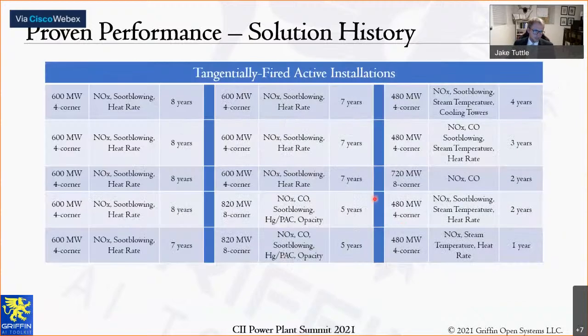Very quickly, just a brief history: we've been doing this over the past 8 years. All of these are closed loop control, meaning the operator simply turns the system on and it's optimizing from there on out, determining the optimal operational parameters. Without the operator having to do anything else, it's controlling the unit within a range of control around the DCS curves.